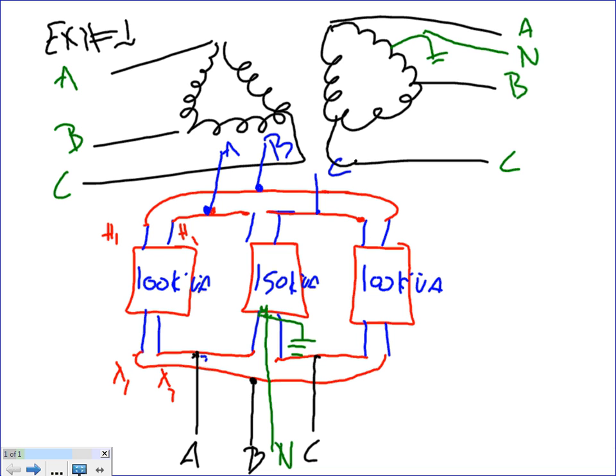100, 150, 100. The voltages, yeah, you're going to ask me what is the voltages. The voltages, guys, we're going to be using for this system. Let's use a 2400 volt on the primary. On the secondary, we're going to be using the commonly used 240/120 volt. We're using a 240/120 volt on the secondary side, 2400 on the primary side. Any question, guys, about that?